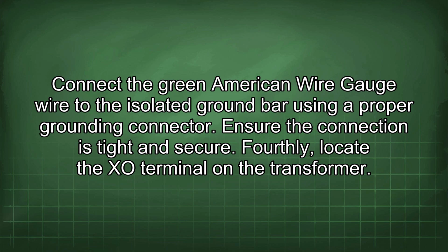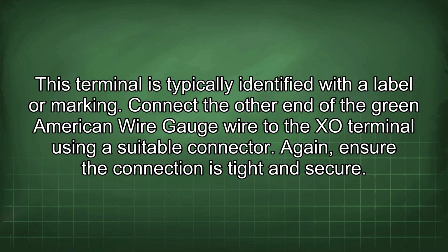Fourthly, locate the XO terminal on the transformer. This terminal is typically identified with a label or marking. Connect the other end of the green American wire gauge wire to the XO terminal using a suitable connector. Then ensure the connection is tight and secure.